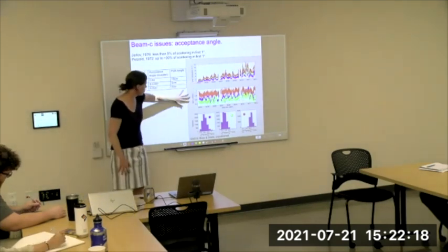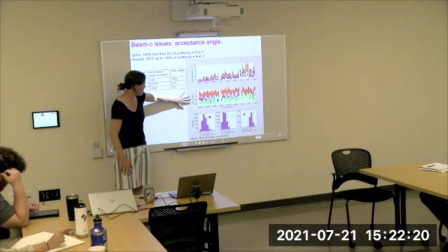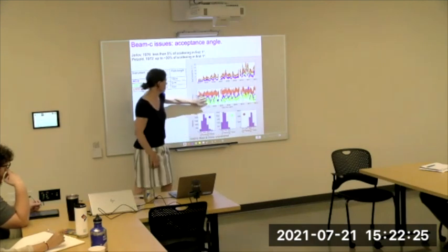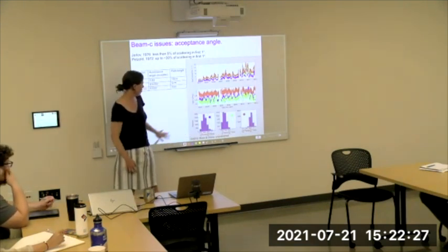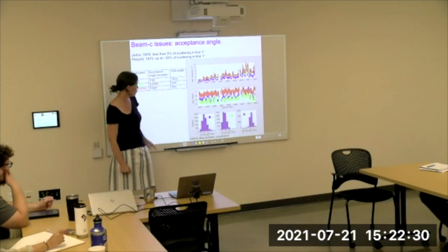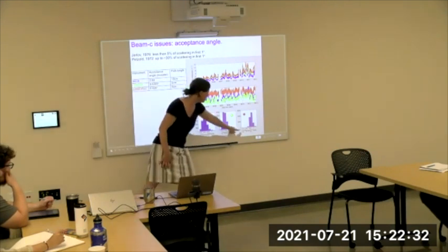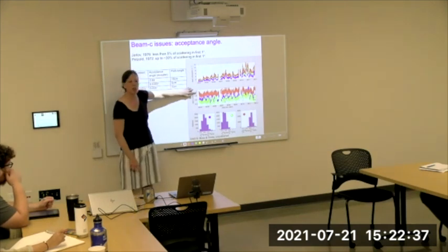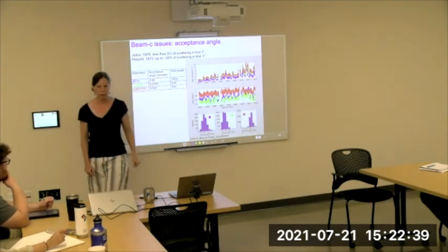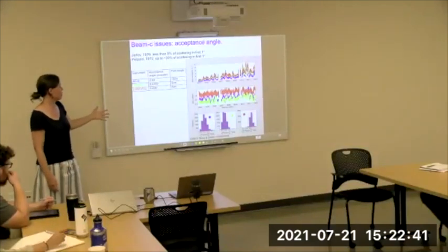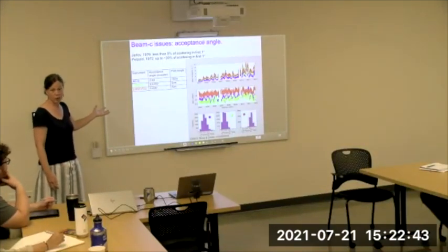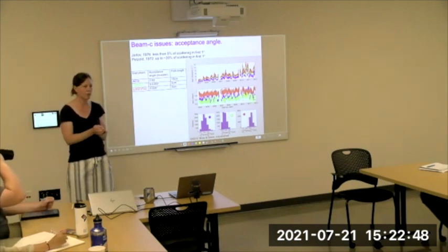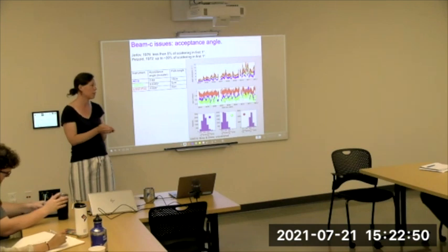We can take the ratios of those different sensors, and here I put little colored dots to correspond to what line in the middle panel we're looking at. But you can see, for instance, that our two LISSTs, which both have their narrowest acceptance angles, have a ratio that's closer to 1, right? So they're doing a better job. But there is no way to correct for this effect. So when you report beam attenuation, you need to report the acceptance angle that goes along with it, because it's an inherent part of what you're measuring.